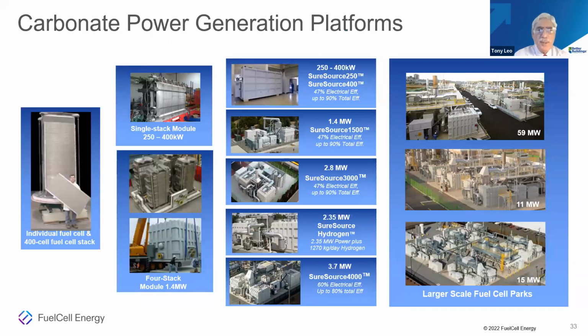This is just an illustration of what the carbonate equipment actually looks like. In the picture on the left, that fellow is holding a single carbonate fuel cell — a fuel electrode, an air electrode, and a thin porous layer between them called the matrix, which holds the electrolyte. There are 400 cells behind him in a stack. Four of those stacks go into our 1.4 megawatt module, manufactured in Torrington, that goes into our megawatt-scale systems. We also deploy single stack systems in Europe ranging from 250 to 400 kilowatts.